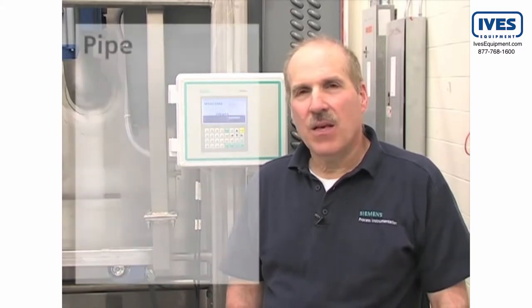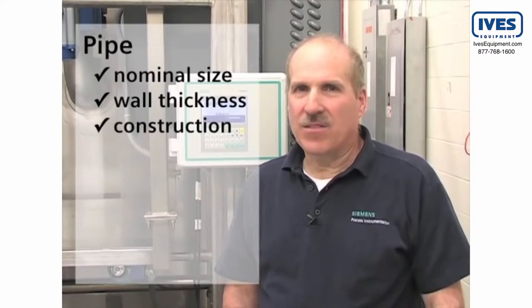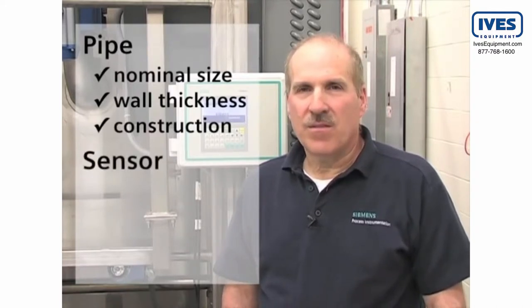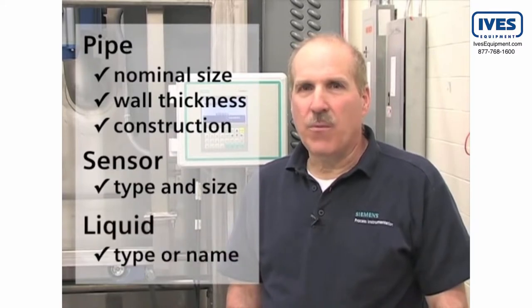To configure the SITRANS FUS1010, we need the following application details: the nominal pipe size, wall thickness, and construction material at the sensor location; the type and size of sensor being used; and the type of liquid we will be measuring.